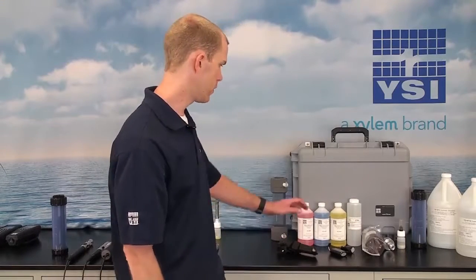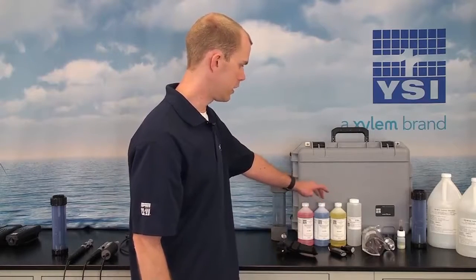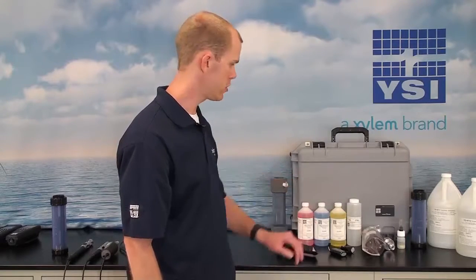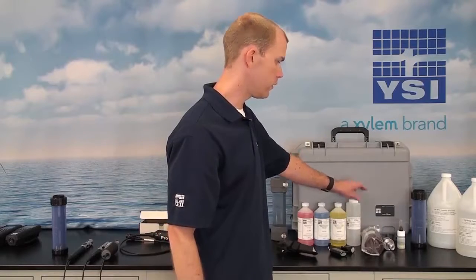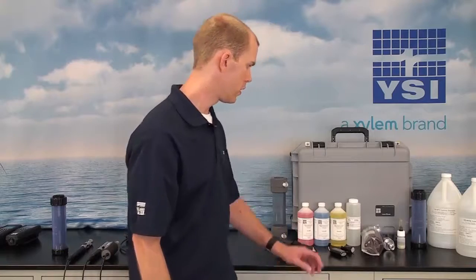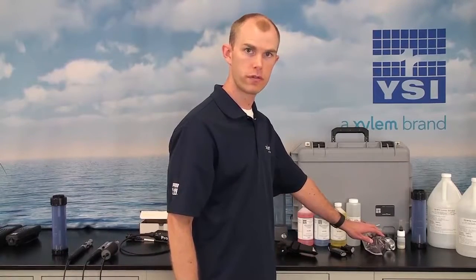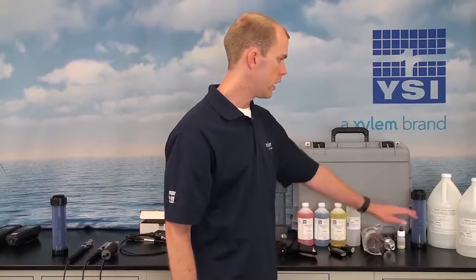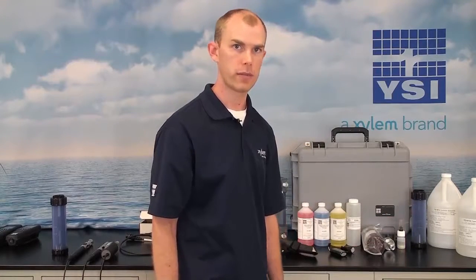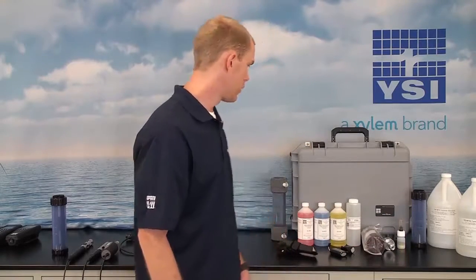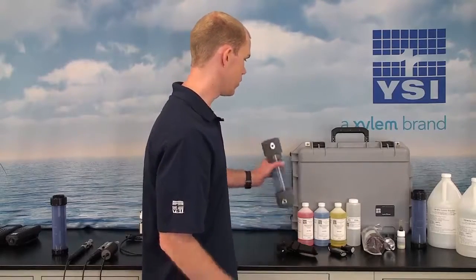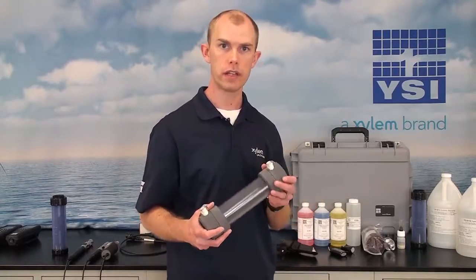So now in the last step in putting together your ProDSS system, I would like to cover the accessories that are available. So we have different calibration solutions. We have pH 4, 7, and 10 buffers for calibrating pH. We have different conductivity solutions that are available as well that go all the way from 1,000 up to 100,000 standard. We have Zobell solution for calibrating the ORP sensor, and then we have turbidity standard for calibrating the turbidity sensor.